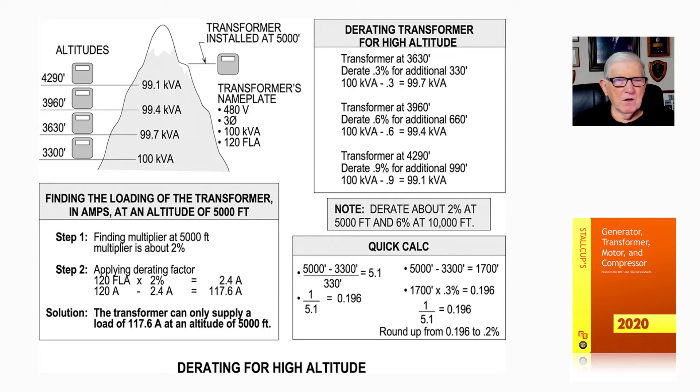Now to determine the amps reduction on this transformer: Step 1, at 5,000 feet, 2% of 120 FLA would be 2.4 amps. 120 amp output minus 2.4, you could load the transformer to 117.6 amps. That would be the loading in amps of the transformer at 5,000 feet. 117.6 amps at 5,000 feet is the solution, and that's what Figure 7-13 is illustrating.